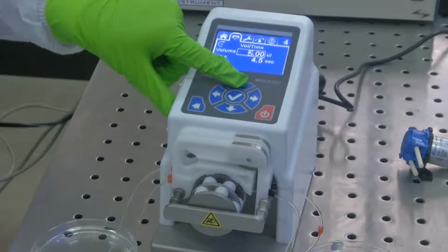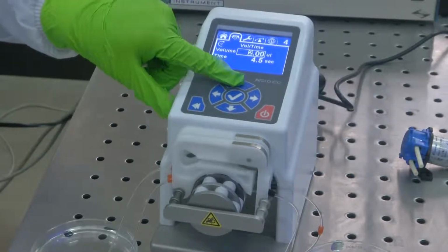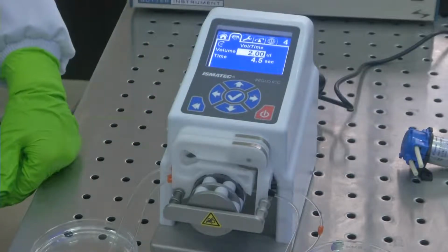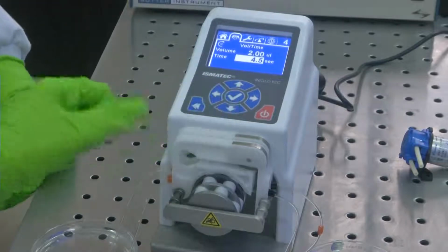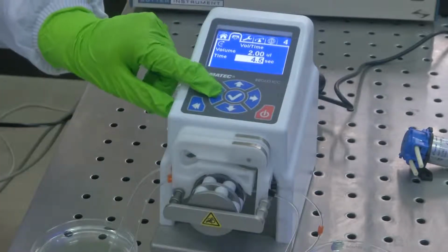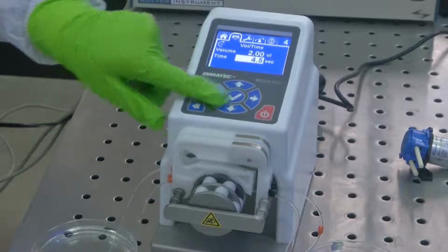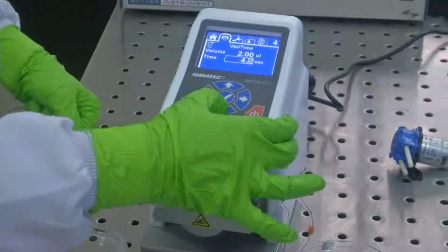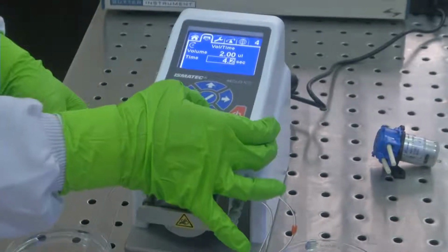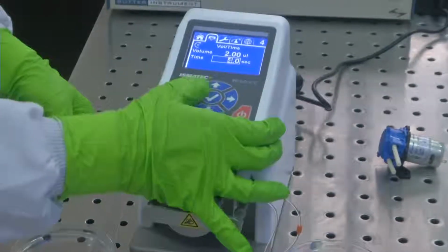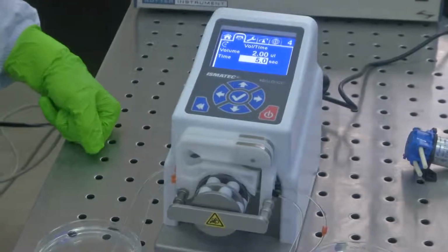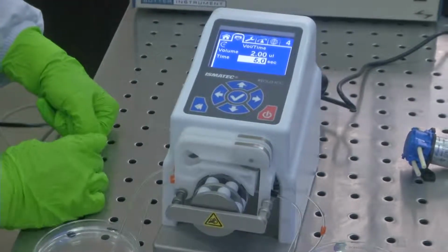So we set it to around 2 microliter, for 2 microliter, say for 5 seconds, because 2 microliter is a very small amount of fluid. So let's say we increase the time to around 5 seconds. Okay.